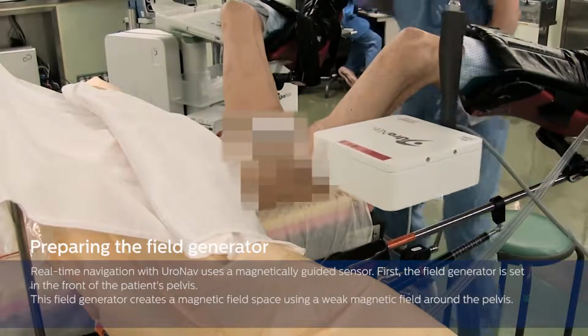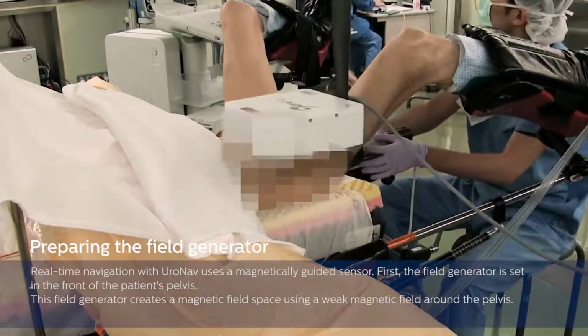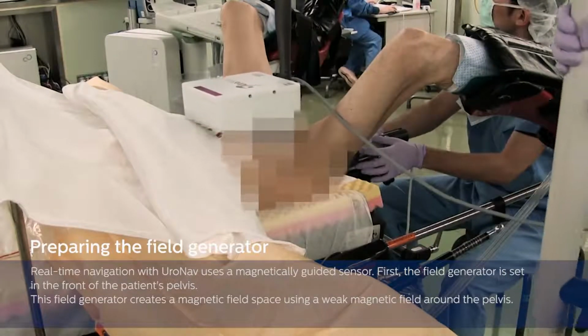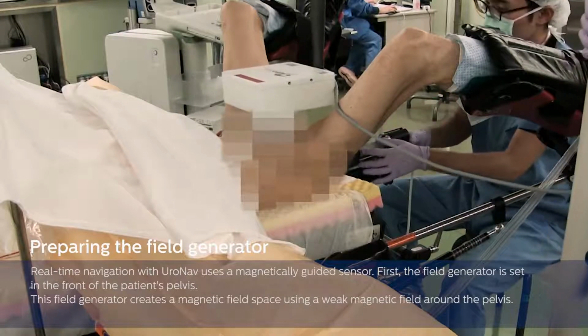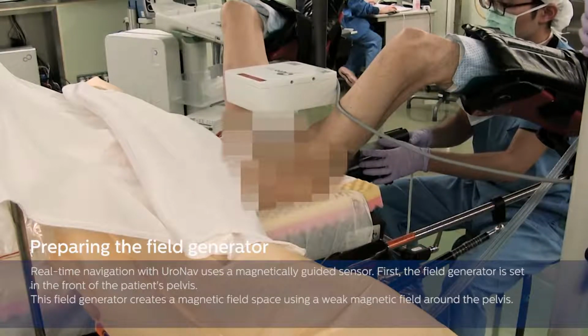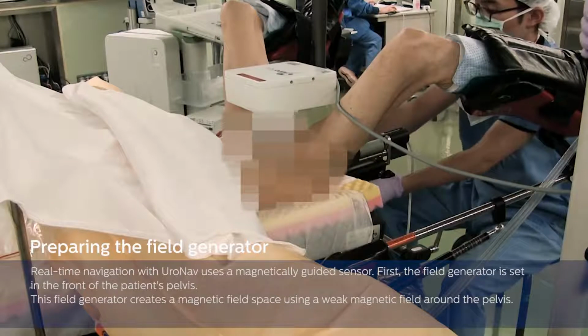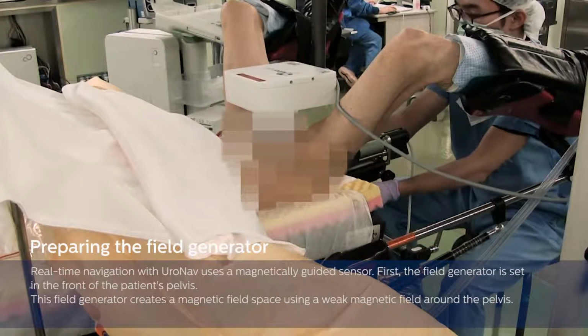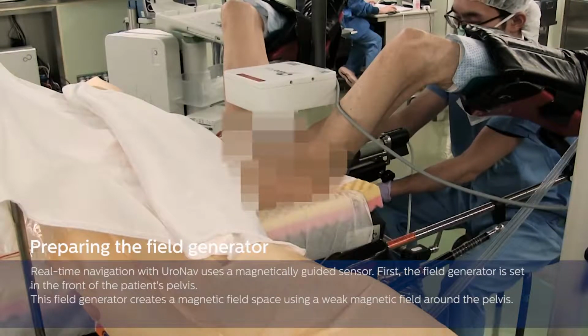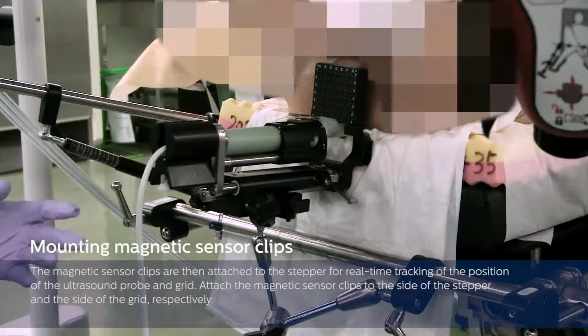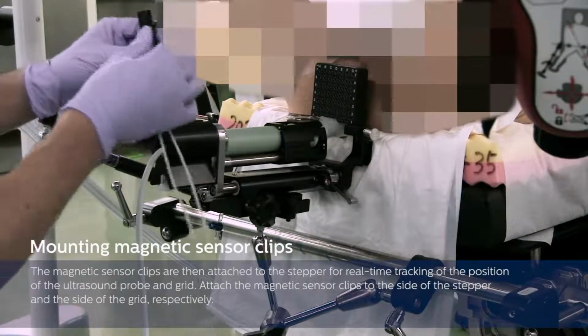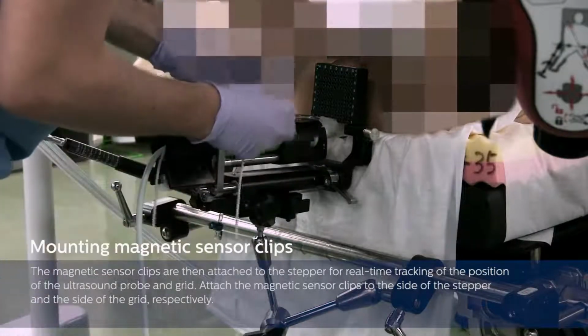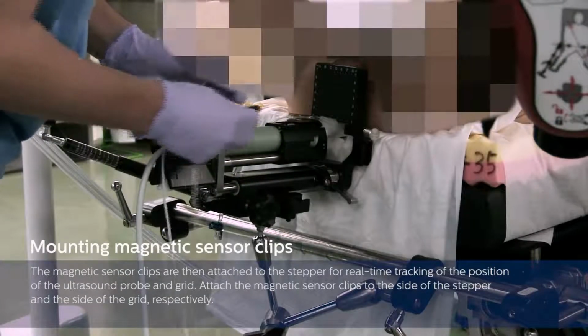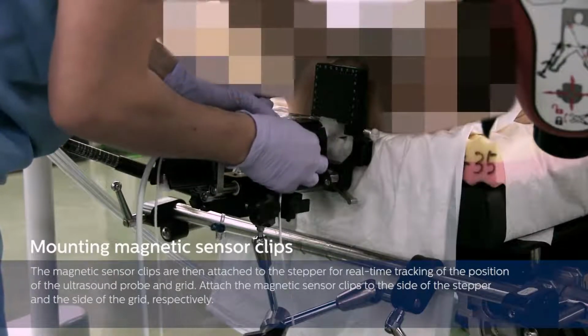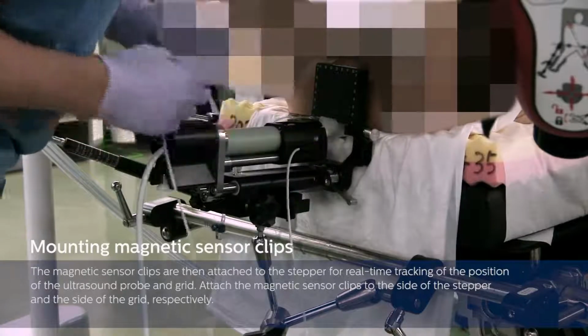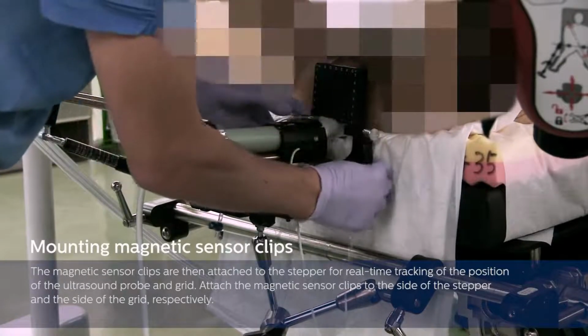Real-time navigation with UroNav uses a magnetically guided sensor. First, the field generator is set in the front of the patient's pelvis. This field generator creates a magnetic field space using a weak magnetic field around the pelvis. The magnetic sensor clips are then attached to the stepper for real-time tracking of the position of the ultrasound probe and grid. Attach the magnetic sensor clips to the side of the stepper and the side of the grid respectively.